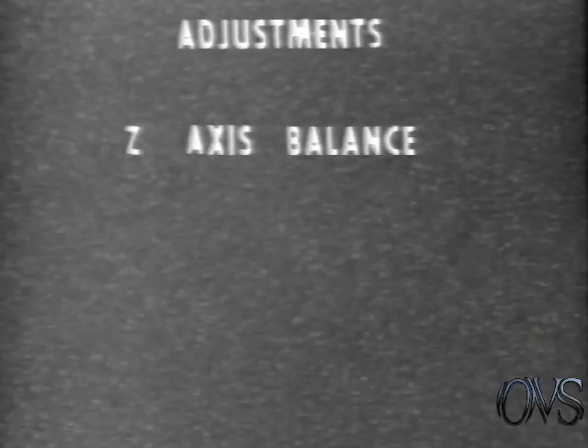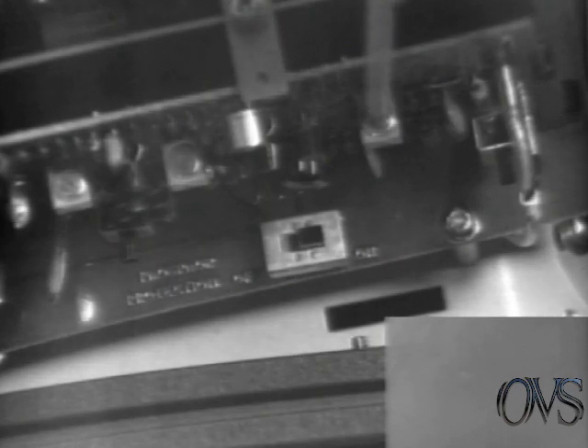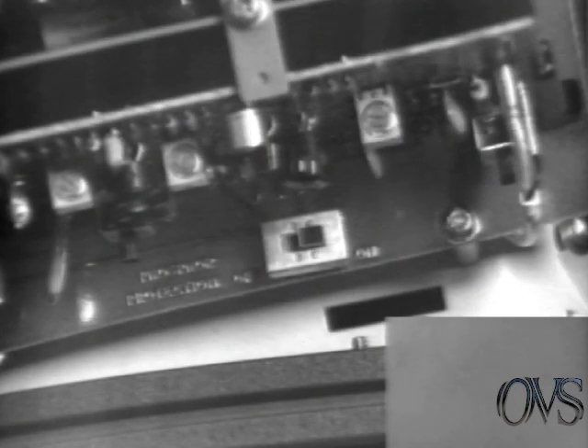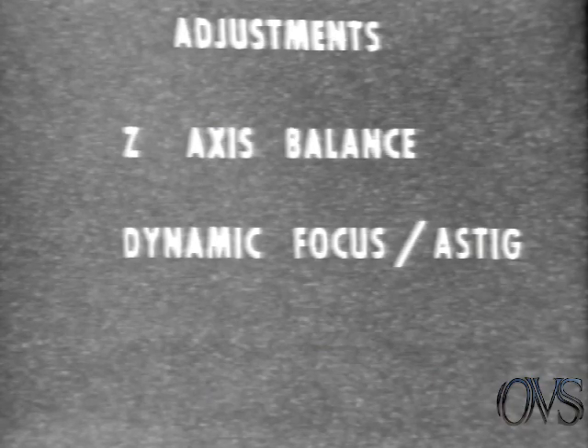Our first adjustment is Z-axis balance. Check to see that the phosphor protection switch is set to on. Now, with no X, Y, or Z-axis signals applied, adjust the intensity control until a dim spot is observed. Next, switch the Z-axis polarity switch between plus and minus while adjusting the Z balance pot for no change in spot intensity between positions. To adjust the dynamic focus and astigmatism circuitry, center the focus and astigmatism controls and position the spot to the center of the CRT.